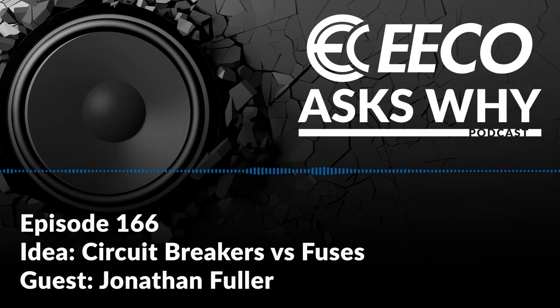You know, it all depends on that application. So if you've got some sensitive electronics or things like that, you're typically going to want to use a fuse to protect that. If you've got just everyday things, you can just use a circuit breaker on those, if they're not very sensitive to inrush currents. But it also depends on the inrush currents in your circuit. If you're prone to a lot of inrush current, it depends on your downstream circuit as to whether you want a fuse or a circuit breaker. It is also going to depend on your application, as far as whether you need combination arc fault breakers for residential, or whether you're going to need ground fault protection, because then you're typically going to want to go with a circuit breaker instead of a fuse. Right, right. Very good.